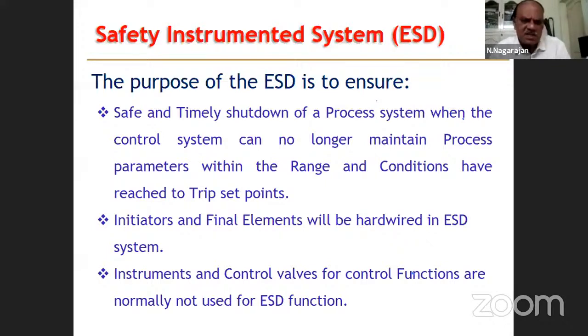So the initiators and final elements will be hardwired in ESD system. Instruments and control valves for control functions are normally not used in ESD. ESD sensors, controllers are separate. Okay, they are not linked to the process control, because we don't want to mess up the two systems. One system, control system, is continuously in operation. That is the major thing which is running the process smoothly. ESD has to come into function only when there is an emergency.